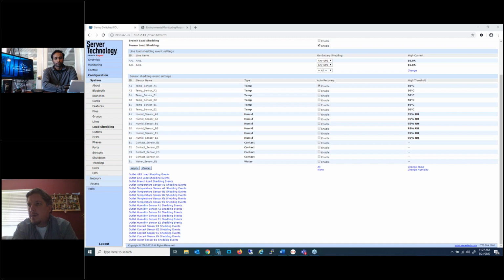The contact closures, by the way, have been used for monitoring, commonly door sensors. So if you have contact closures on your cabinet doors, we've actually had people use those as emergency power off switches. If their cabinet security is compromised and that door is opened without being on a schedule, then the equipment could all turn off, which could be a safety measure if you're looking at a security incident where somebody is attempting to compromise your devices. That'll be the trigger. Okay. At a physical level, yeah.